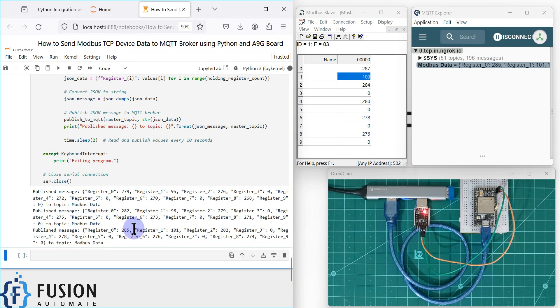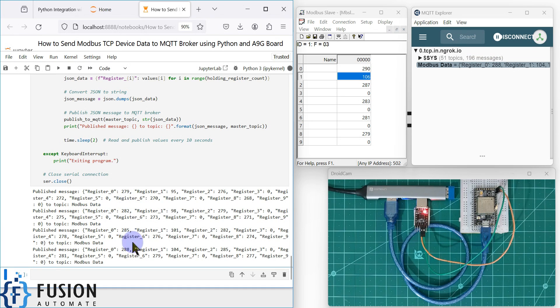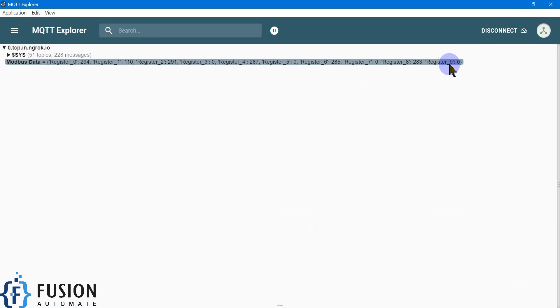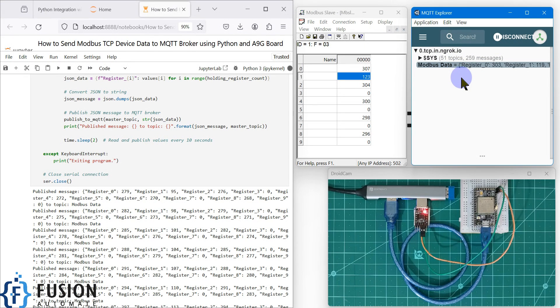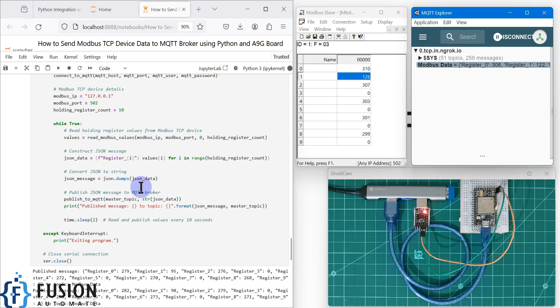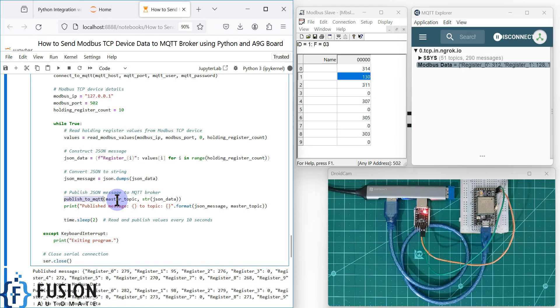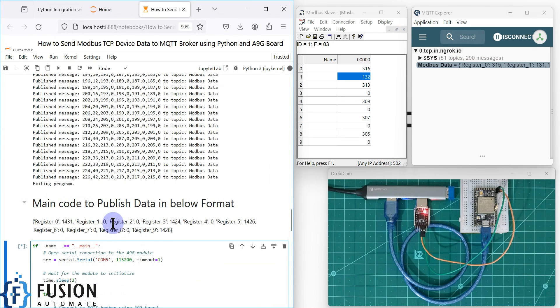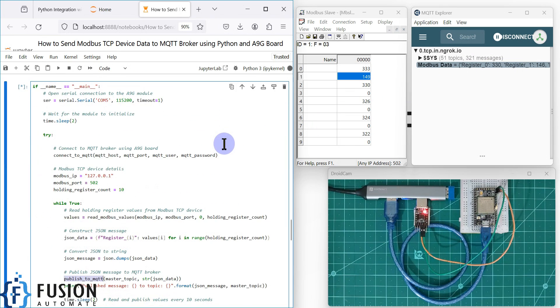Every two seconds the data updates. You can see register 0: 261, register 1: 177, and so on. In MQTT Explorer you can expand the payload and see the full values from register 0 to register 9 — all values available in a single request. If you have 100 holding registers, you can publish all 100 values in one request without calling the publish-to-MQTT function repeatedly. If you use Node-RED or a SCADA server you can extract the JSON and differentiate register values, passing them to tags.